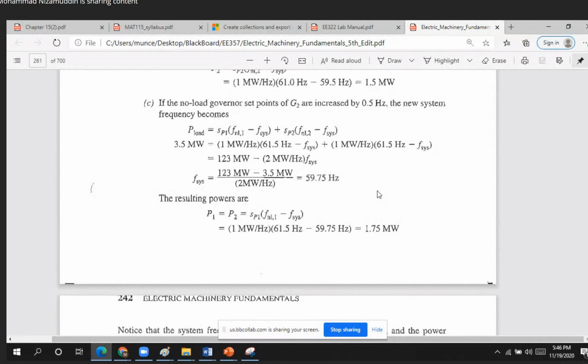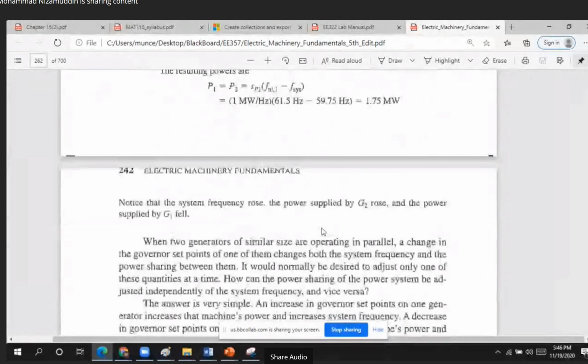This happens only when few generators are working for the system. If thousands of generators work in the power system, considering an infinite power supply, the frequency will not change. What might change is the amount of power your generator is sharing if the system load is changed.